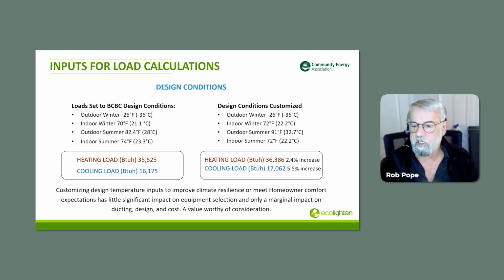So in this case, your heating load might be 36,000 if you customize it. That's in the coldest conditions in the winter. In some places, the spring and fall is a lot different. In your shoulder seasons, you don't need a fraction of that capacity. And that's where the variable refrigerant really makes a difference. It just adapts to the load condition, and therefore it's extremely efficient. It's very quiet.